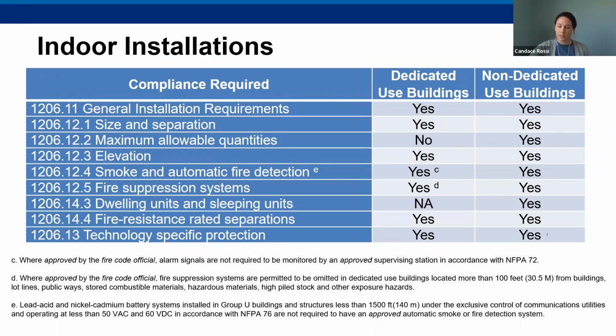And you can see down here where it gets to 1206.14, those are the specific ones for indoor installations, which we'll talk on the following slides. And then also has the requirements for the technology specific protection, which is what we just went over, which is based on the requirements specifically for a lead acid or lithium ion. And then you can see for non-dedicated use buildings that all of these requirements are necessary. And that has a lot to do with a higher threat to human health, as if this is being installed in a college or building that is used for mixed use, you want to make sure you have as many required protections in place as you can.